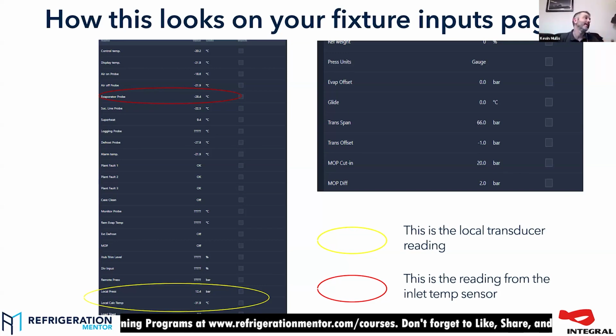Yeah. The problem you'll have then is that the valve goes into startup, starts pulsing a load of liquid in, but you've got a heck of a lot of heat to absorb before that inlet probe understands what the inlet temperature of the coil is. Because the coil's hot, you've actually got a ton of superheat, but because that probe hasn't seen any liquid yet, it doesn't know. It thinks it's got no superheat. So depending on how long your controller gives the valve to start up, at some point, if it doesn't see liquid by then, it's going to go, no superheat, and it's going to stall. So a lot of the time, controversially, perhaps for some controller manufacturers, it is, in my opinion, better to have it as near to the inlet of the coil as possible, because it gives you more reliability on startup.